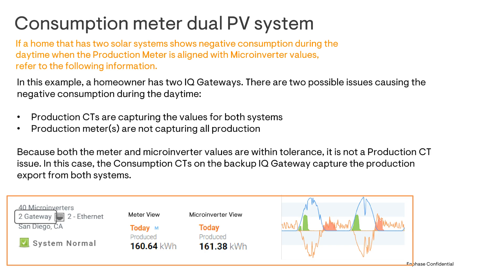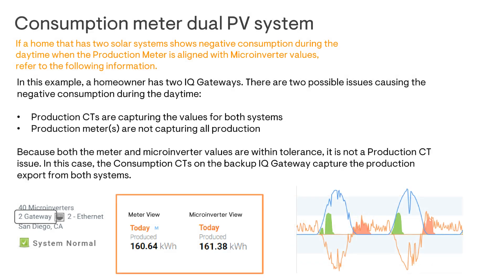In this example, a homeowner has two IQ gateways. There are two possible scenarios that can result in negative consumption during the daytime. One scenario is if the production CTs are capturing the values for both systems. The other scenario is if the production meters are not capturing the total production from both PV systems. You'll need to compare microinverter values against meter values and adjust if needed. Check out the link in the show description for instructions on how to compare microinverter values and meter values.